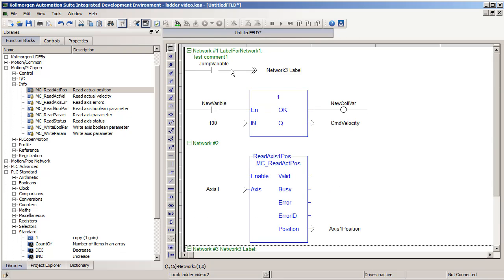As a general rule, I like to tell people that it's fine if you jump down or forward in your program, but we tell people it's best not to jump up or backwards. The reason being is you can quickly get into a semi-infinite loop. It doesn't take long with KAS running at the EtherCAT update rate not to be able to run in, say, a millisecond or faster that your program's trying to run in. So, once again, as a general rule, just jump down, don't jump upwards.